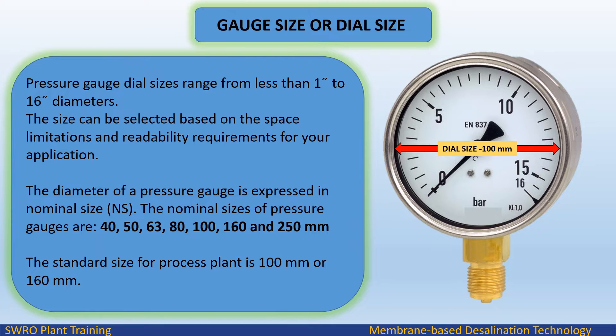Gauge size or dial size: Pressure gauge dial sizes range from less than 1 inch to 16 inch diameters. The size can be selected based on space limitations and readability requirements. The diameter is expressed in nominal size, with standard nominal sizes of 40, 50, 63, 80, 100, 160, and 250 millimeters. The standard size for a process plant is 100 mm or 160 mm.